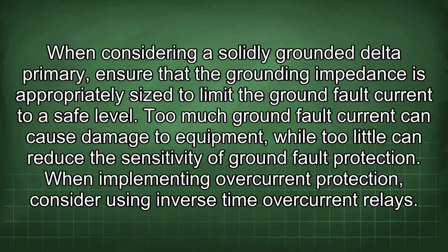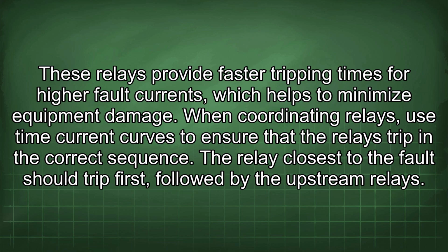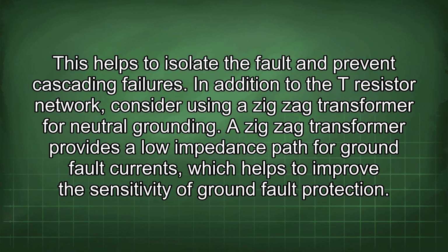Too much ground fault current can cause damage to equipment, while too little can reduce the sensitivity of ground fault protection. When implementing overcurrent protection, consider using inverse time overcurrent relays. These relays provide faster tripping times for higher fault currents, which helps to minimize equipment damage. When coordinating relays, use time current curves to ensure that the relays trip in the correct sequence. The relay closest to the fault should trip first, followed by the upstream relays. This helps to isolate the fault and prevent cascading failures.